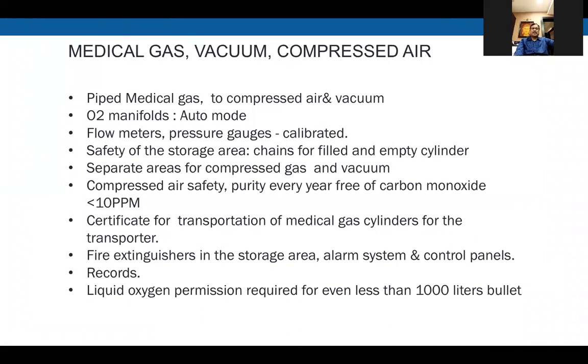The area for compressed gas and vacuum has to be physically separated from the manifold. Many of the hospitals have not complied with this, but slowly, after NABH inspection and all, I think they are undergoing changes. This is purely from a safety point of view. Again, compressed air, we have specified under NABH guidelines also that it should be checked every year. It should be free of carbon monoxide and free of humidity. That's why we have put dryers there. Many times what happens is the dryers are not cleaned properly, they get neglected, and you will start getting water in the ventilators, and patients will feel very uncomfortable. So this is compressed air also. Safety is of paramount importance, and preventive maintenance of all these facilities is a must.